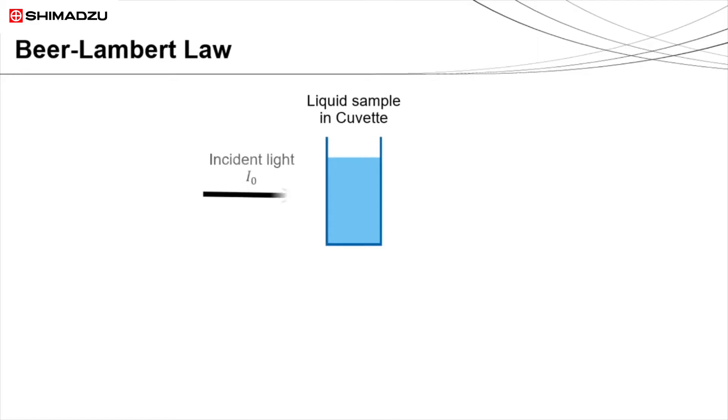When incident light passes through a sample, the sample in the cuvette absorbs the light. The amount of light that is not absorbed by the solution will come out as transmitted light. Transmittance is the ratio of the intensity of the transmitted light beam to the intensity of the incident light beam and is commonly expressed as a percentage. If there is no absorption of the light passing through the solution, the transmittance is 100%.